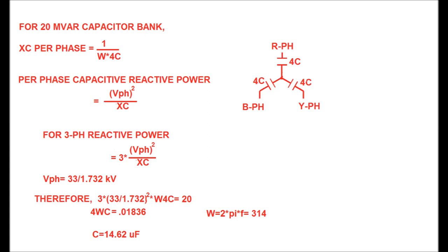The equation becomes: 3 × (33 / 1.732)² × ω × 4C = 20 MVAR. Solving, 4ωC = 0.01836. With ω = 2π × 50 = 314 rad/s, solving this equation gives C = 14.62 microfarad.